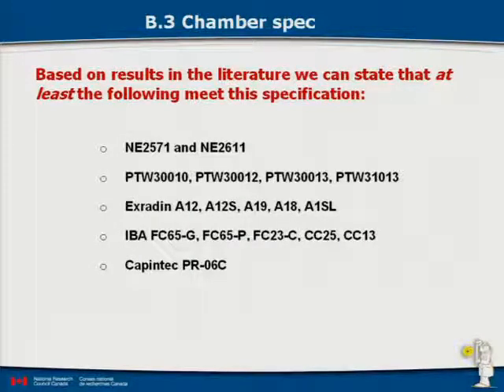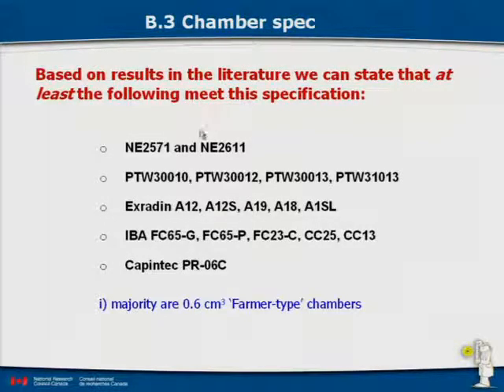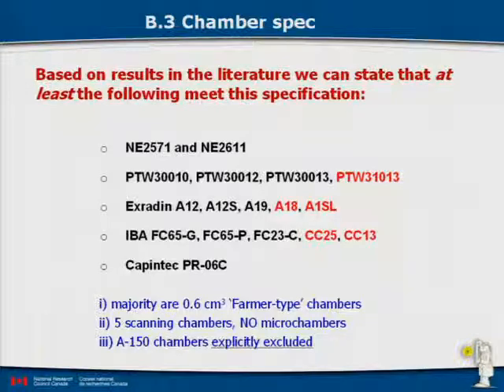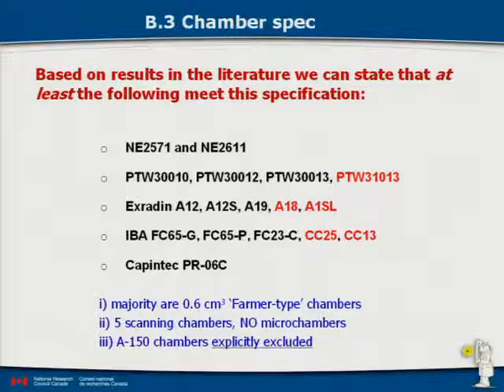Based on that chamber spec, the chambers that meet the requirements include mostly 0.6 cc farmer chambers, and five scanning chambers. No microchambers and no A150 chambers meet reference class. The reason A150 is excluded is that it's hygroscopic, and data in the literature show large variations depending on storage conditions and environment, making it very difficult to monitor the stability of the calibration coefficient.